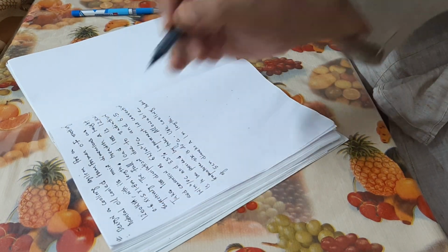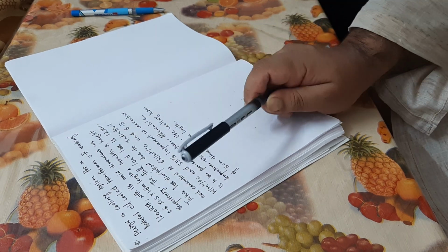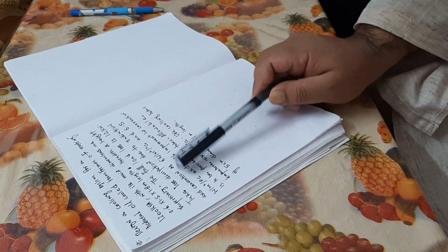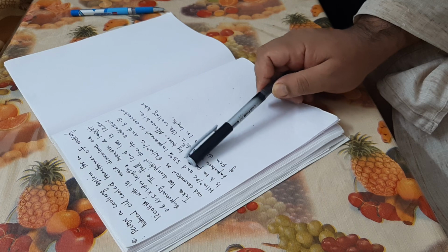So the second problem which we'll be seeing states: design a cooling system for a natural oil cooled transformer of rating 1200 kVA with its main dimensions as 0.6 into 1.5 into 1.8 meter. The dimensions are length, breadth and height respectively. The full load loss is 12 kilowatts. Take loss dissipation due to radiation and convection as 6 watts per meter square per degree Celsius and 6.5 watts per meter square per degree Celsius, and 35% improvement in convection is to be provided by tubes.